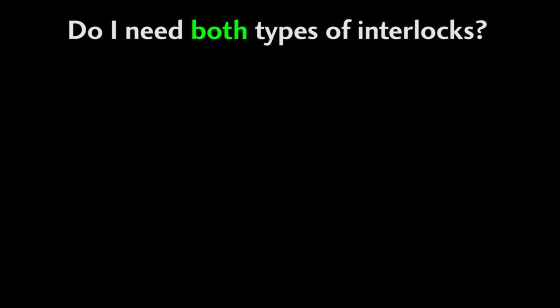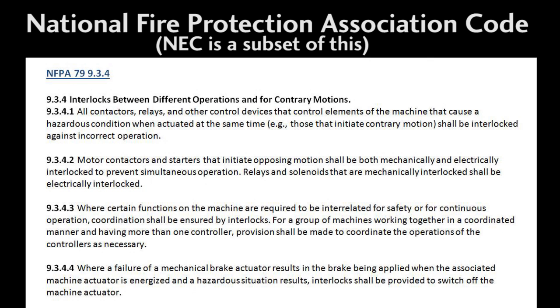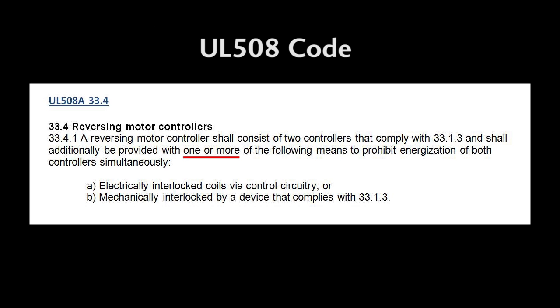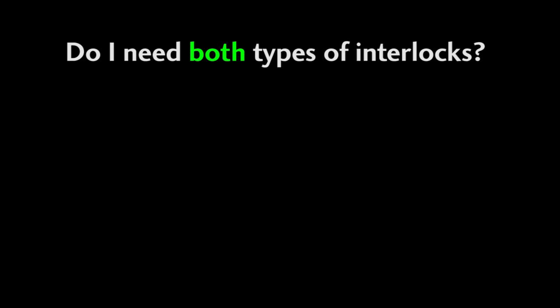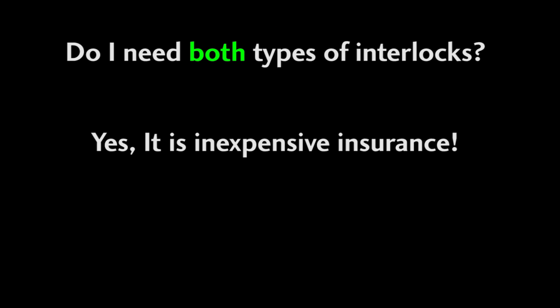Do you need both types of interlocks? Well, that depends on your application. For example, the National Fire Protection Association Code, which the National Electrical Code is a subset of, does require both kinds of interlocks when contactors are used for opposing motion. UL508, on the other hand, requires one or more interlocks. And since they are so cheap and easy to do, why wouldn't you do both? It's an inexpensive way to protect your valuable equipment.